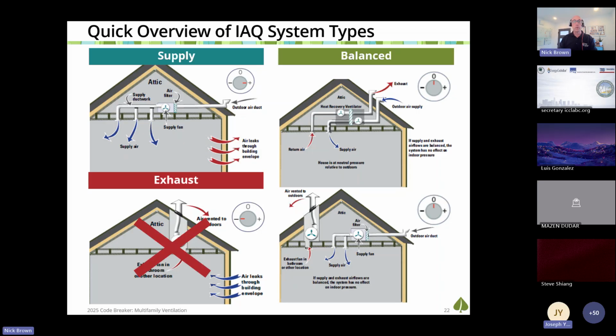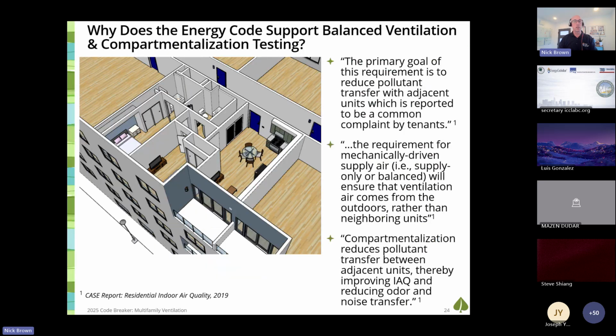Yes, Jorge, for single family under section 150, single family still allows exhaust. But remember, low-rise multifamily no longer lives in section 150. So low-rise multifamily is governed by this new requirement along with high-rise multifamily. This occurs in sections 160 and 170.